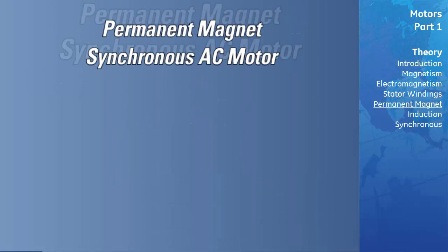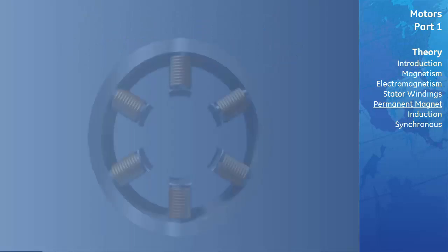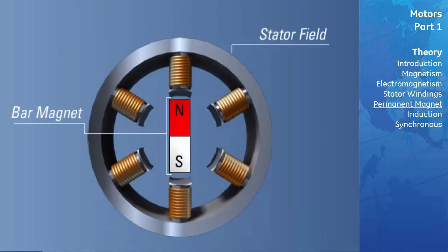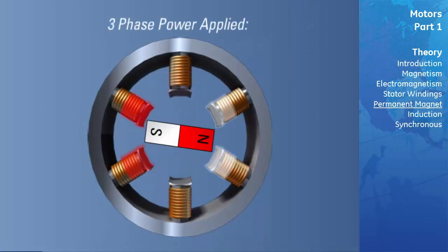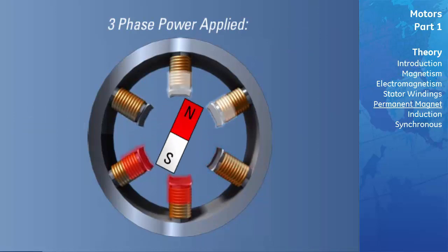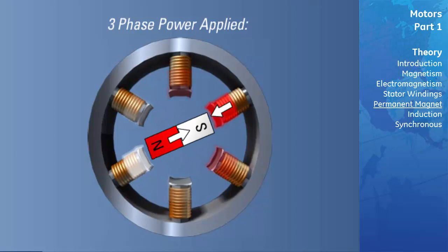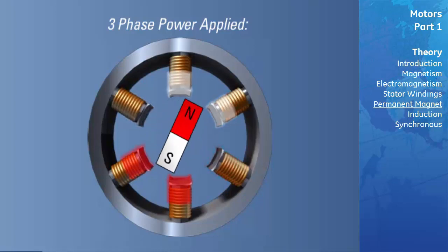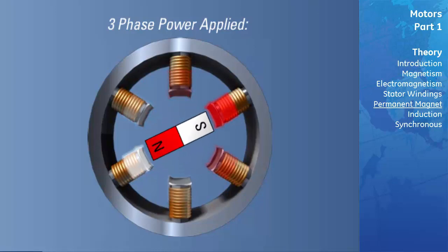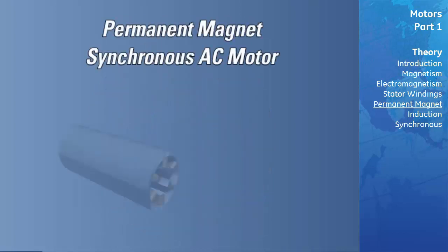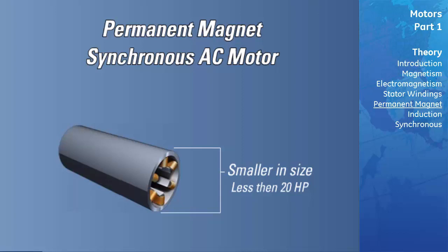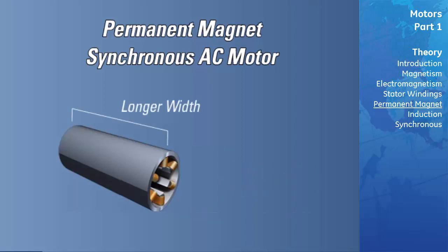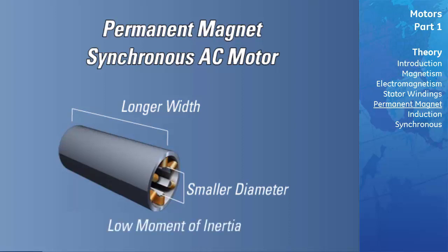Now let's take a look at the operation of a permanent magnet synchronous AC motor. First, we will mount a bar magnet in the center of the stator such that it can rotate freely about its own axis, as shown. Then we will apply three-phase power to the stator, and note that the stator's rotating magnetic field will form. Opposite poles of the bar magnet and stator field will attract each other, resulting in the production of torque, which will cause the bar magnet to rotate at the same speed as the stator field. Permanent magnet synchronous AC motors tend to be very small — from fractional horsepower to less than 20 horsepower — with a very low moment of inertia, making them ideal for high-speed positioning applications such as motion controllers.